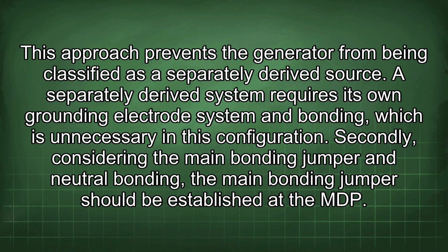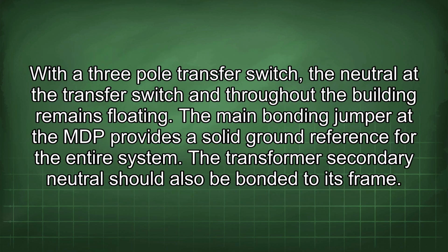Secondly, considering the main bonding jumper and neutral bonding, the main bonding jumper should be established at the MDP. With a 3-pole transfer switch, the neutral at the transfer switch and throughout the building remains floating. The main bonding jumper at the MDP provides a solid ground reference for the entire system.